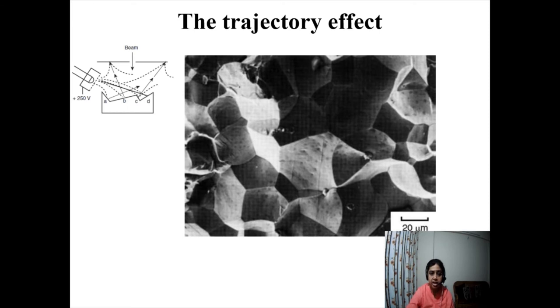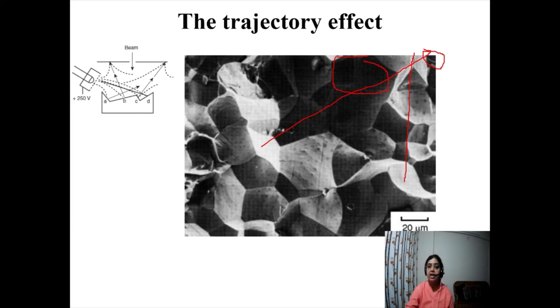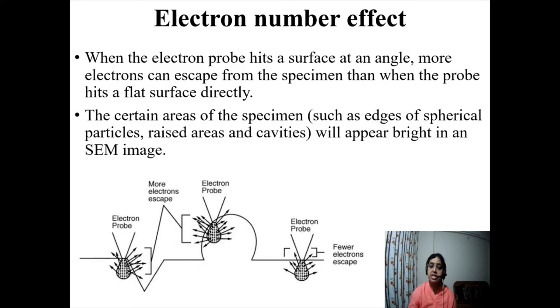You can see that areas directly facing the detector appear brighter — because more electrons are reaching the detector from there. Areas that are not facing the detector appear dull. In this image, the brighter areas indicate surfaces facing the detector, and the dark areas indicate surfaces facing away. This is the trajectory effect creating topographical contrast in the SEM image.